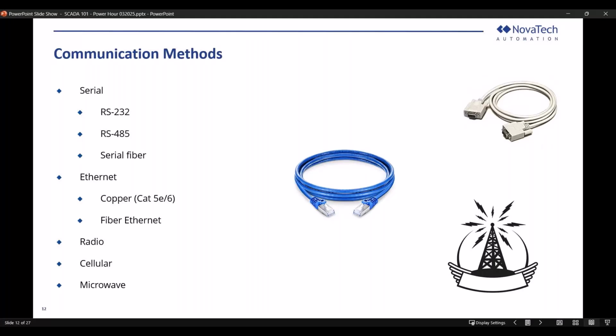RS-232 and RS-485 are pretty common. As a refresher, if people don't know the difference, 232 is peer-to-peer, so one device to another. You've got your one client and then your one device that serves data to it. It transmits one bit at a time. Baud rate, you hear baud rate a lot in serial communication. 9600 is pretty common. That means 9600 bits per second. Connector-wise, the one in the picture here is the DB9. Some serial RS-232s are DB25s. You might even see RJ45, which is this cable, which is confusing because it looks like Ethernet but is actually serial. It's very rare, but it does happen. RS-232 is usually for short range, mostly because it's very susceptible to noise.